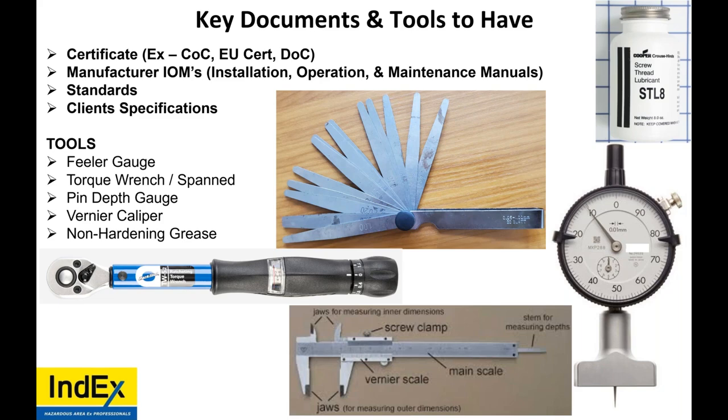If we drill a cable gland in an explosion-proof JB on site, is a certification required? Flameproof. You cannot drill a flameproof enclosure. Okay? You in the field, you on site, you cannot drill it. You are not allowed. Certification, the safety of it is completely compromised. Do not do that. Please do not do that.